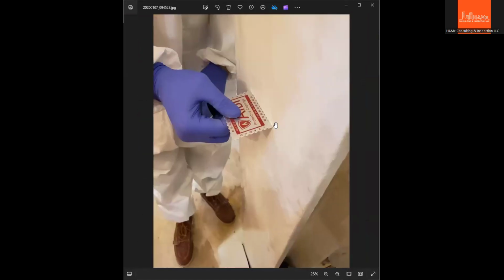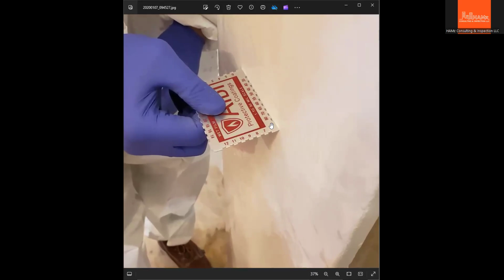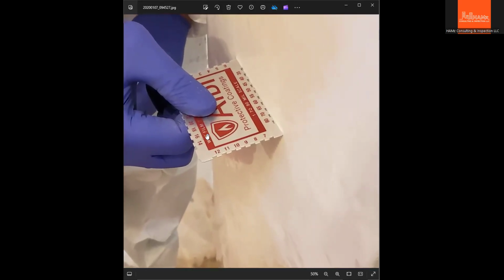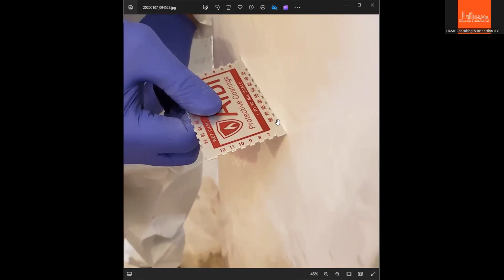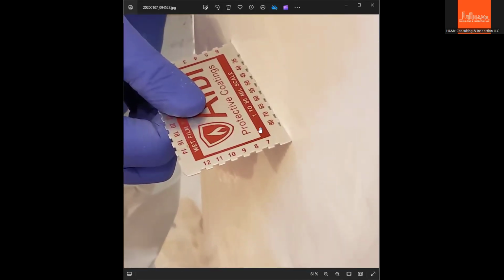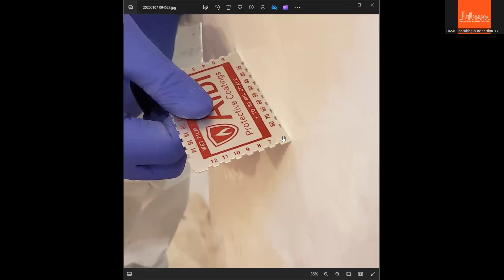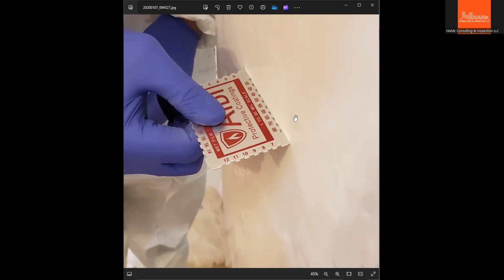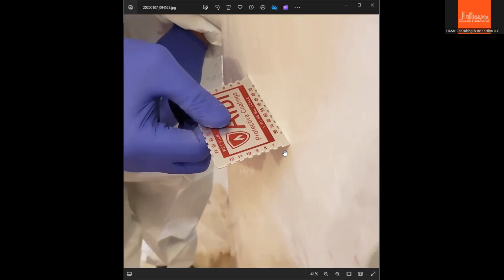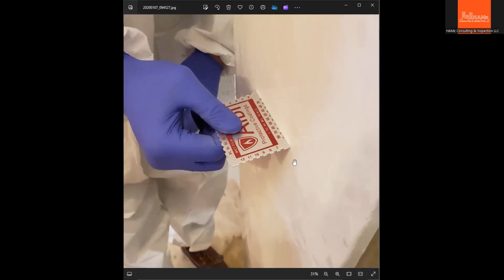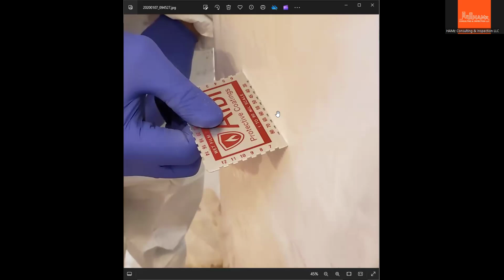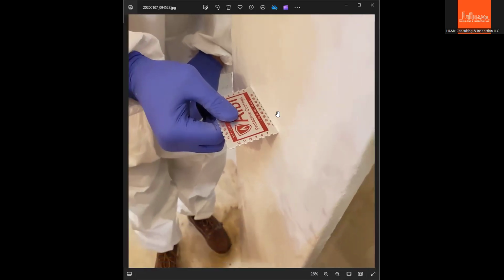It will take time for it to cure. So in the submittals or the supporting documents of the material, there is a specified film thickness to acquire. So this is the wet thickness application. You don't need to exceed the specified wet film thickness as per the approved documents or supporting documents of the material, because it might fall down, or it might not have the correct thickness for it to cure in a certain amount of time. I think for a required thickness, there's a particular equivalent time for it to cure for another layer to be applied.